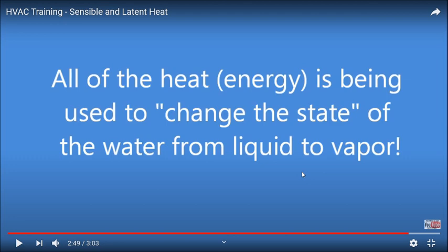This is where air conditioning comes in. The evaporative coil that the air from your home blows through, that's inside your garage, your attic, or in a closet, or it could be outside in a package unit, that evap coil is where the refrigerant boils off around 40 degrees. Yes, refrigerant boils at 40 degrees. So it stays at 40 degrees and it keeps accepting more and more and more heat until that liquid refrigerant turns into a vapor and the latent heat is over with. But as long as it's a refrigerant in a liquid form, the latent heat will stay at that one spot.